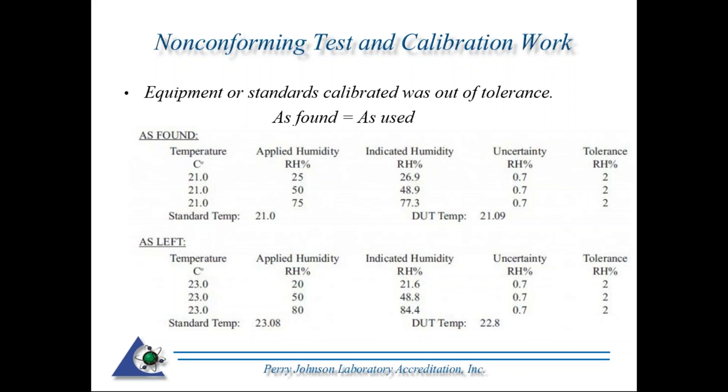The other thing is when instruments or standards, artifacts are sent in for calibration, you typically would get as found and as left data. As found, and I like to call this also as used, is actually how the equipment was found prior to being calibrated.